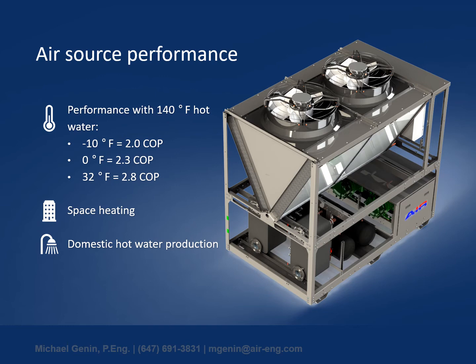So as you can see, as the ambient temperature moves from, let's say, a design condition of -10 Fahrenheit up to 32 Fahrenheit or so, the COP, or coefficient of performance, gets better. And what that essentially means, if you have a COP of 2 at your design condition, for 1 unit of electrical input, you're getting 2 units of heat. So it is essentially twice as efficient as using just straight up electricity as a source of heat. And that's really why air source heat pumps are becoming more popular.